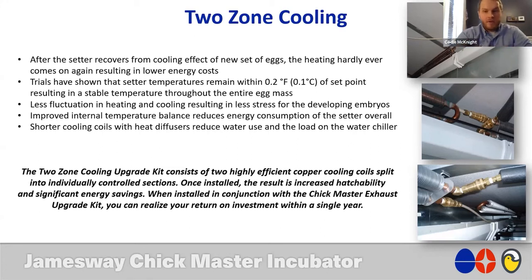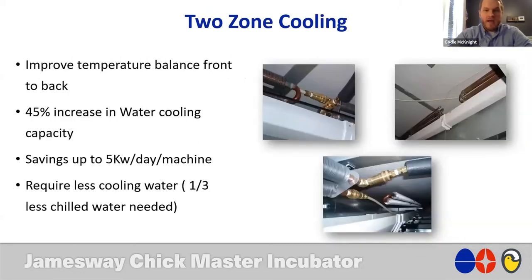On this next slide, we will go through the actual data, the things that we have received from customers that have implemented this upgrade. So along with improving the temperature balance and the control you have inside of your incubation cabinet, you get a 45% increase in water cooling capacity, savings of up to 5 kilowatts per day per machine, and you require less water to cool your machines. So that's less stress on your chiller. All of that greatly increases your efficiency.